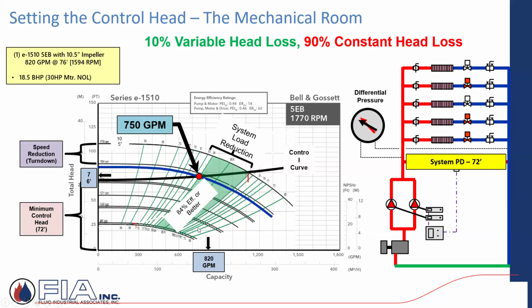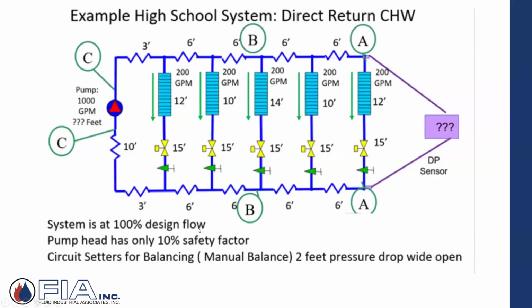So here's a turn down. It's there, but it's not much, and it's because I've established a minimum control head right in the mechanical room. So I've really reduced my variable, really increased my constant. You typically don't want to do that.